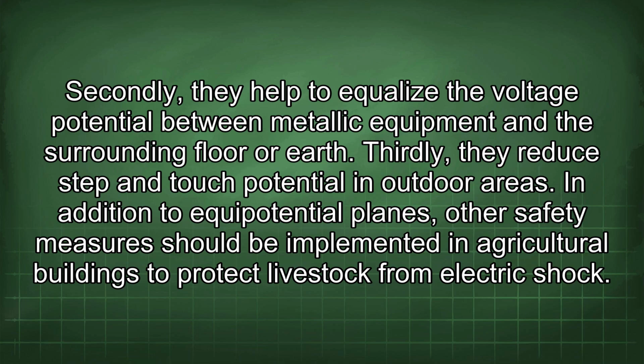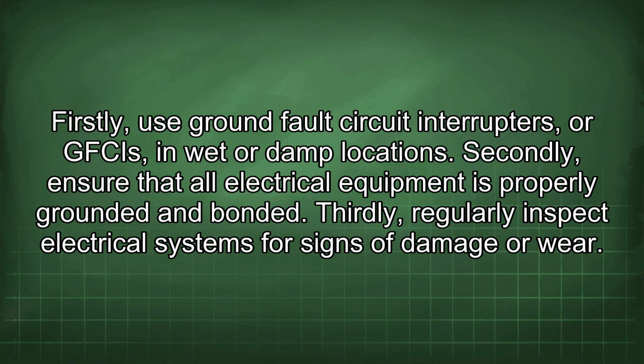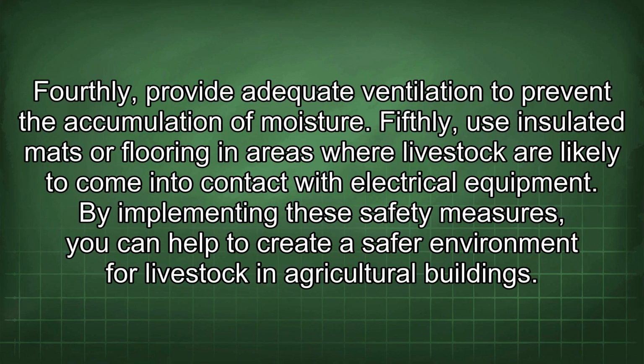In addition to equipotential planes, other safety measures should be implemented in agricultural buildings to protect livestock from electric shock. Firstly, use ground fault circuit interrupters, or GFCIs, in wet or damp locations. Secondly, ensure that all electrical equipment is properly grounded and bonded. Thirdly, regularly inspect electrical systems for signs of damage or wear. Fourthly, provide adequate ventilation to prevent the accumulation of moisture. Fifthly, use insulated mats or flooring in areas where livestock are likely to come into contact with electrical equipment. By implementing these safety measures, you can help to create a safer environment for livestock in agricultural buildings.